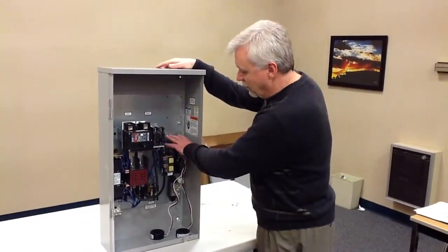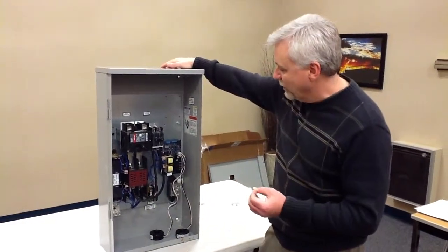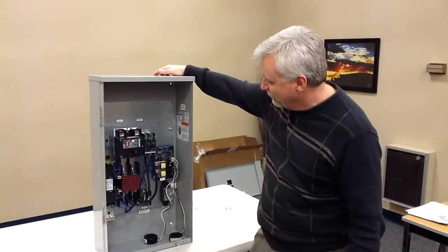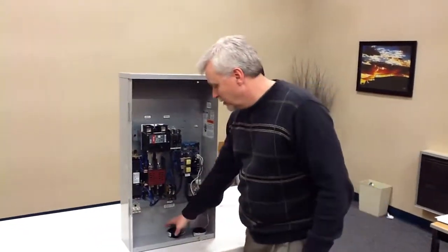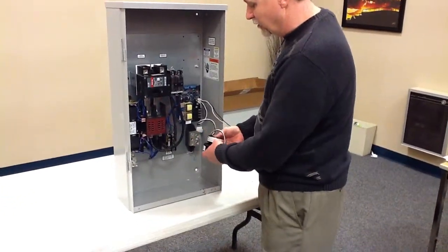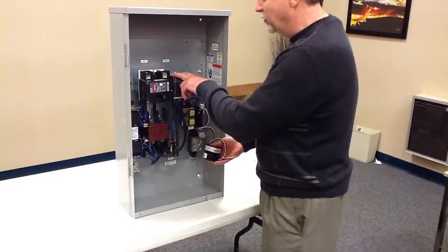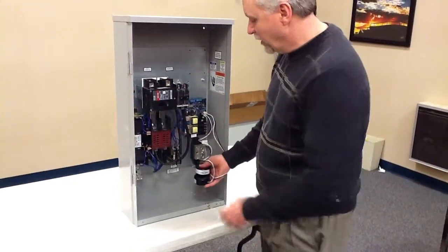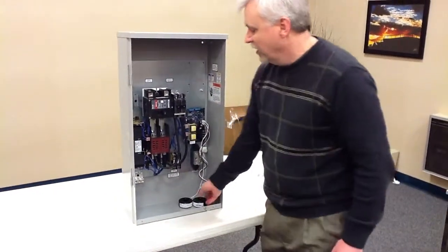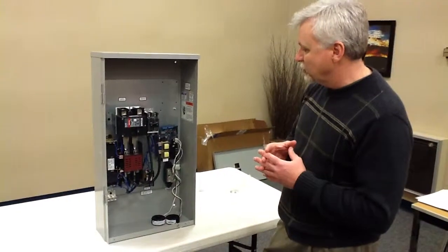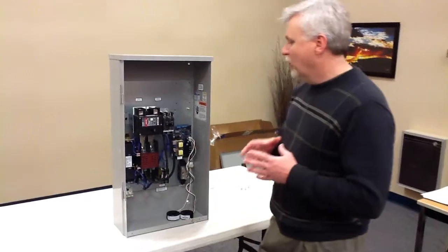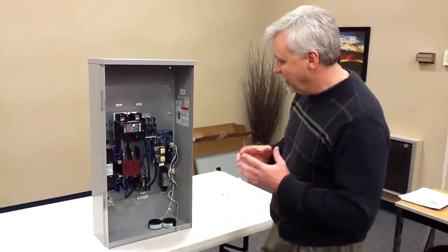So the first piece of knowledge that this board has attained at this point is what size generator is out there and what its output capacity is. The second thing we want to pay close attention to is the current transformers. Current transformers are going to go over the load conductors coming from the generator into your transfer switch here, so it can at all times monitor how much current is actually being consumed in the home. So you have the A component, which is what the generator is capable of outputting, and you have the B component, which is what it is currently taking as a load.